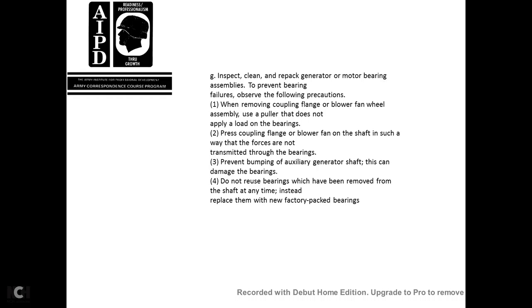One, remove the coupling flange and blower fan wheel assembly using a puller that does not apply force to the load of the bearings. Two, press the coupling flange and blower fan onto the shaft in such a way that the force is not transmitted to the bearings. Prevent bumping of the auxiliary generator shaft, which could damage the bearings. Do not reuse a bearing which has been removed from the shaft at any time; instead replace it with new factory-packed bearings.